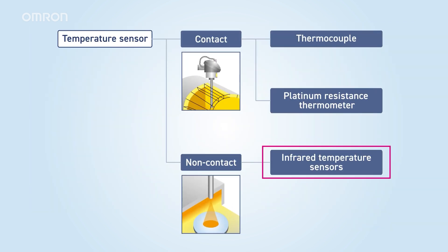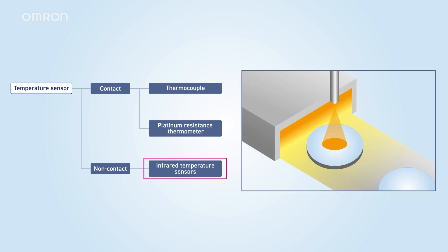Lastly, let's explain infrared temperature sensors. These sensors estimate temperature by measuring the infrared radiation emitted by an object. They are used for measuring the temperature of moving objects, or objects whose quality may change upon contact, such as semiconductors and food. However, accuracy may decrease when measuring metals with low emissivity. Click here for the details about our infrared temperature sensors.